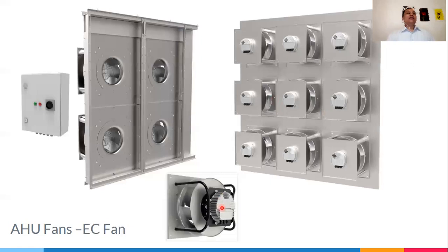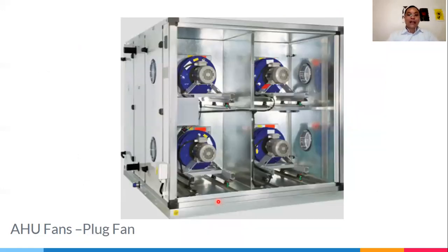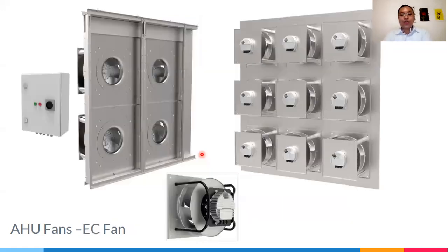These DC fans eliminate the need for a variable speed drive. Because it's DC, you can now input simple commands like 4 to 20 milliamps, and it will run according to the speed you require. So it's like a variable speed drive, kind of like a plug fan, well not quite the same. It is a plug fan, but instead of using an AC motor, you're using a DC motor.